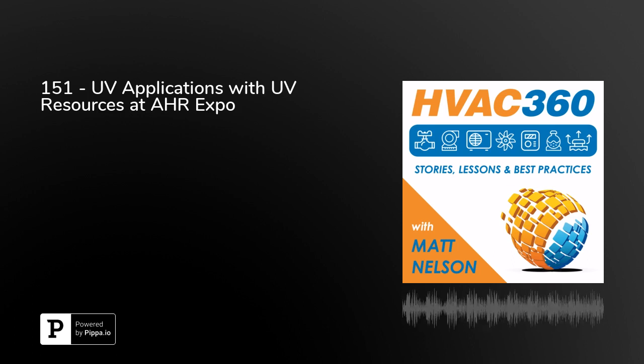Are there applications where UV is misapplied, or that engineers shouldn't consider? Pretty much any HVAC application could use UV—it comes down to what you're trying to accomplish. For surface irradiation, like on coils, there's virtually no coil that wouldn't benefit from UV. The other application is killing something on the fly in a moving airstream, and you have to separate those two. UV works on a time and intensity basis: irradiating a coil, we're on 24/7/365, so we have a lot of time and don't need much intensity. But for an on-the-fly application killing something moving past, you don't have much time, so you need a lot of intensity.